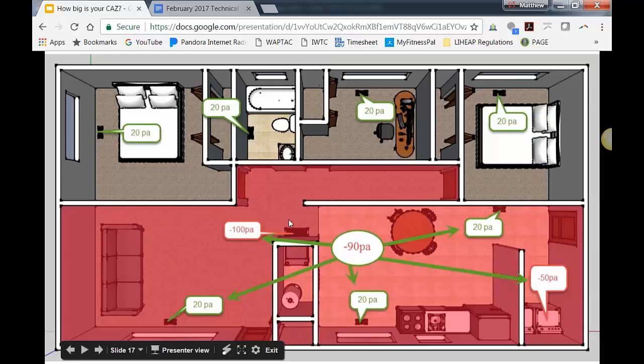And in that case, the pressure inside of this zone was pushing under the door, or there was just a hole, and there was negative pressure outside. There's all kinds of things that can cause the air in this room to move out through that hole in the window or through the air conditioner. But if we were going to have a rule of thumb, it'd be to look at your forces inside of each of those zones and think about whether this zone could be positive or negative based on those forces. If you're not sure, measure them.